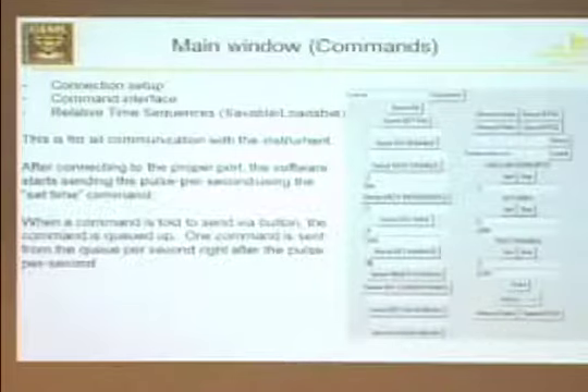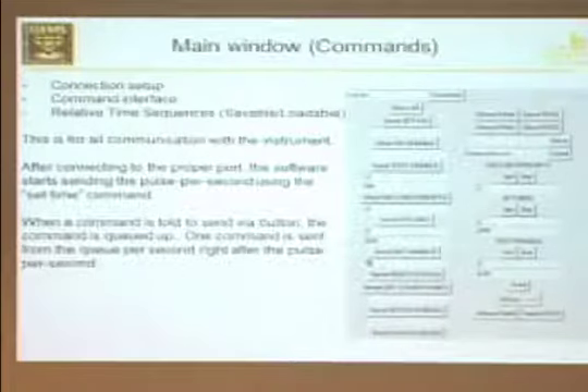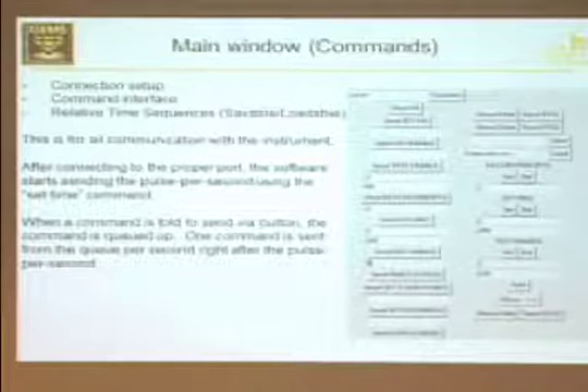Each time you click the send button, it puts that command in a queue that would go to the device. Over a bit to the right of that, you see the relative time sequences. With this, you can basically set a series of commands to be sent in order as soon as you send that relative time sequence. Now, the pulse per second starts as soon as you connect to the device.